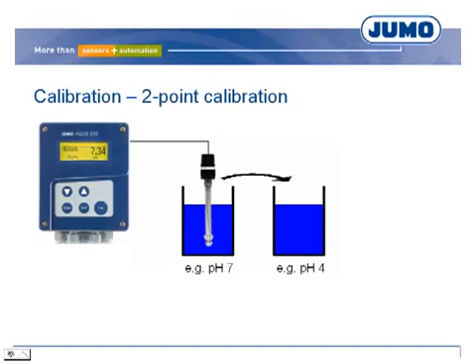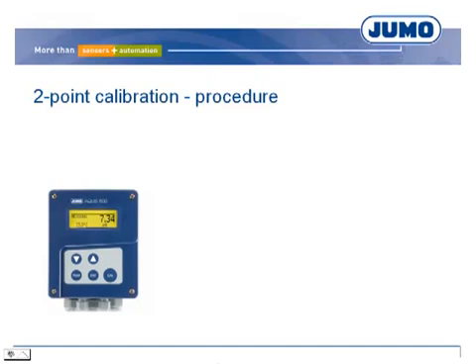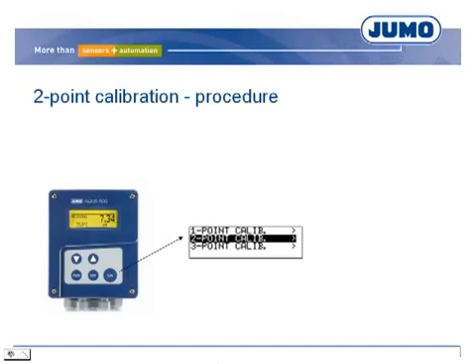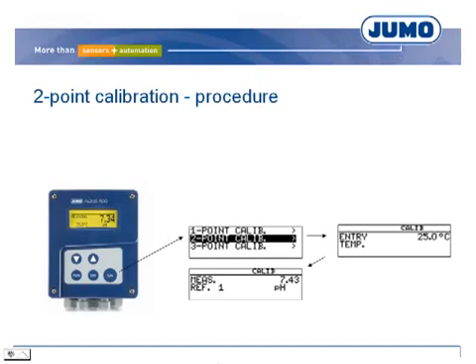For the two-point calibration, the buffer solutions must be placed in separate vessels and the electrode rinsed with distilled water. The combination electrode is put into the first buffer solution, for example pH 7, and two-point calibration is selected. When no temperature sensor is used, the temperature of the buffer solution must be measured and entered into the transmitter — this is especially important when the calibration point is far from pH 7. The transmitter shows the measured pH value, and the pH value for the current temperature, found on the bottle of buffer solution, must be entered into the transmitter.